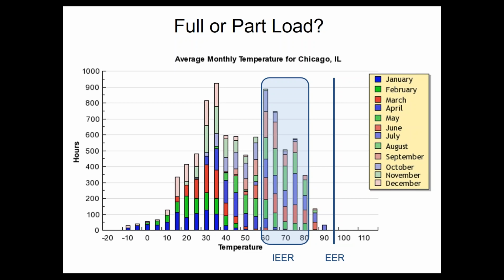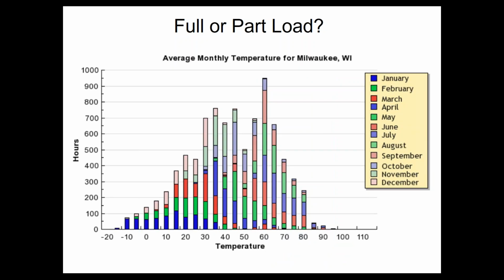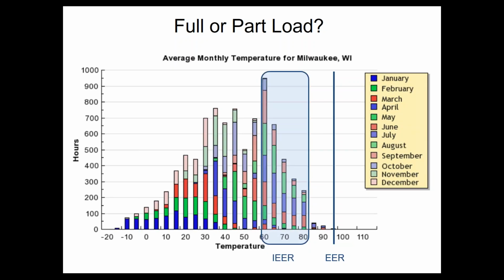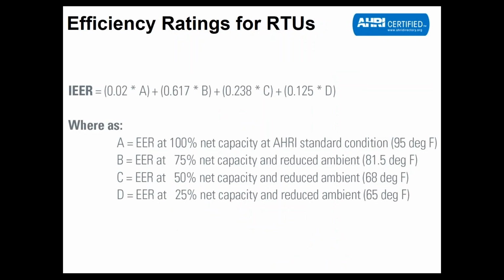Tell me that. Same thing if I'm looking at Milwaukee, same kind of discussion. I don't care about a 95-degree day. How efficient are you on these other days, 60 to 90 degrees, if you will? I don't really care much below that because then I'm probably in economizer mode. So how efficient are you on these days? Because of that, EER is being replaced with IEER, Integrated Energy Efficiency Ratio. So what happens there is that they do the EER test at 100% capacity on a 95-degree day. Then they do another test on a partly loaded 75%, 50%, and 25%.